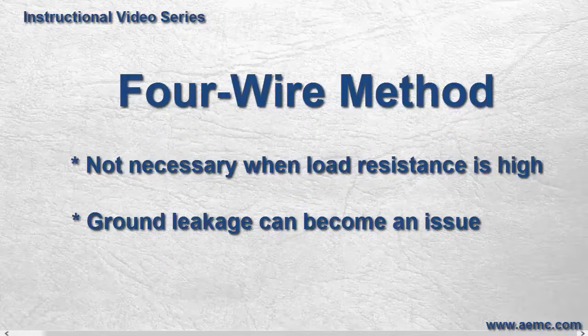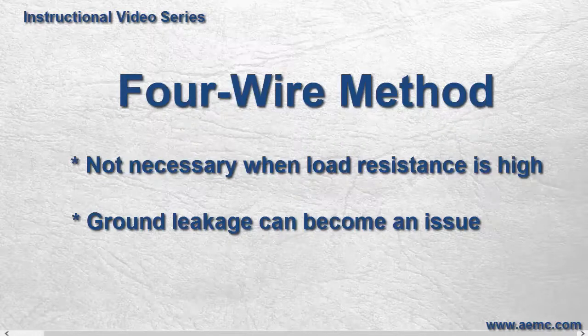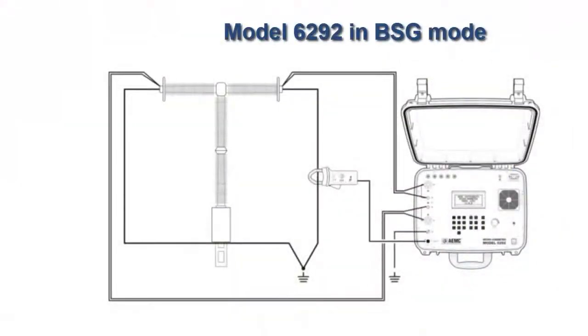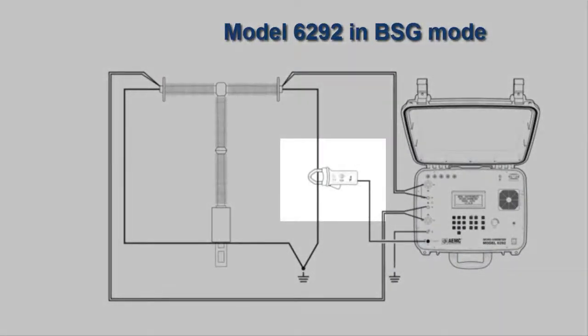The model 6292 mitigates the problem of ground leakage by offering a mode called Both Sides Grounded or BSG mode. In this mode, the model 6292 uses an external DC current probe to measure and eliminate ground leakage current from the total test current.